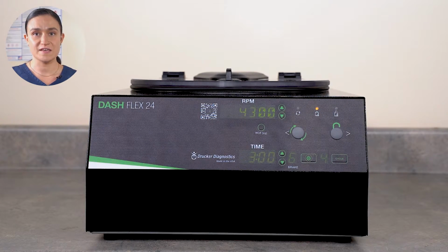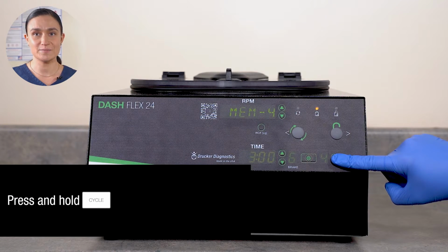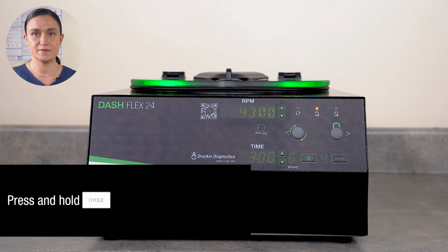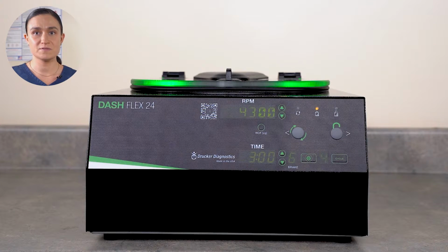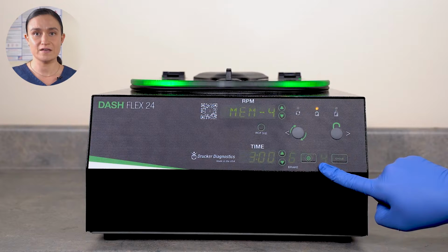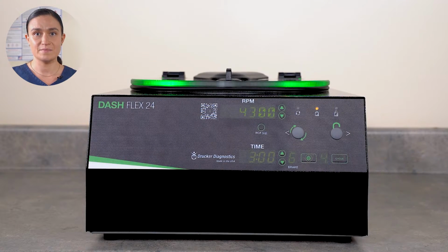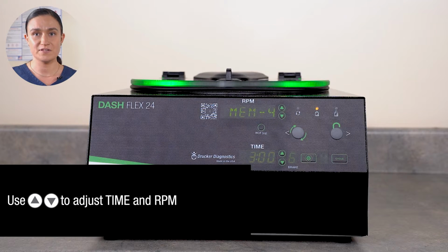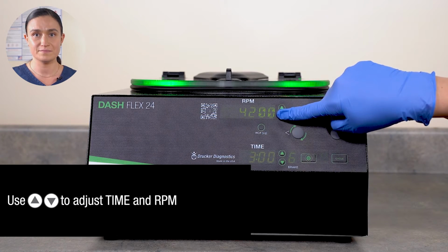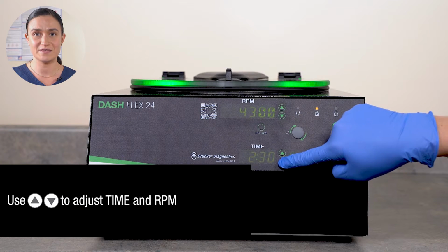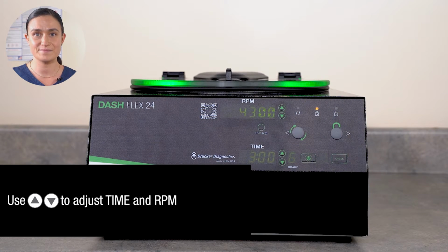Once you have the saved cycle you want to rename selected, press and hold the cycle button. You'll hear a beep. The centrifuge lights will turn on and the number next to the cycle button will blink. That means you're in edit mode. If you want to edit your RPM or time, you can do that right now. Just adjust up and down using the arrows next to each display.